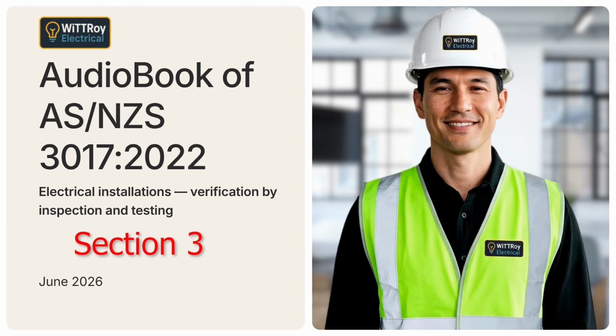For consumer mains, the conductors must be clearly identified to show their intended function. In simple terms, we need to know which conductor is active, neutral, earth, or other required function. The installation wiring system condition must also be checked. For underground systems, check items such as enclosure, depth of burial, and mechanical protection. For aerial systems, check items such as mechanical protection, support systems, and whether cables are likely to be disturbed.